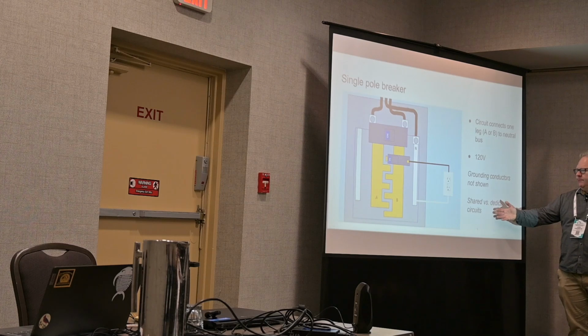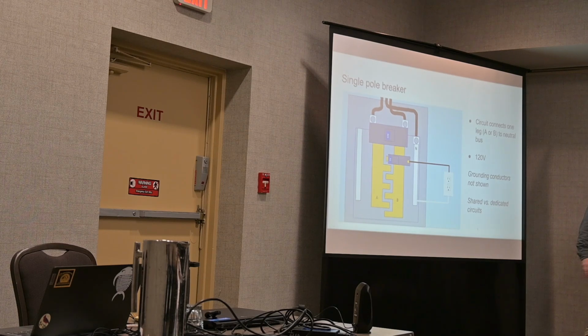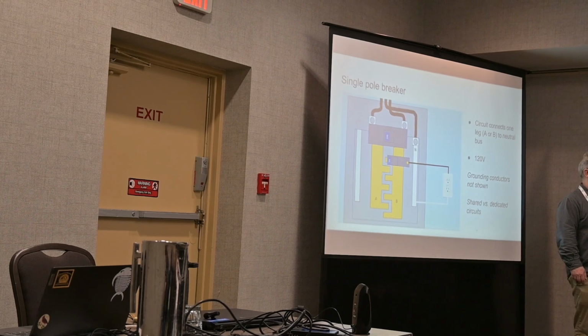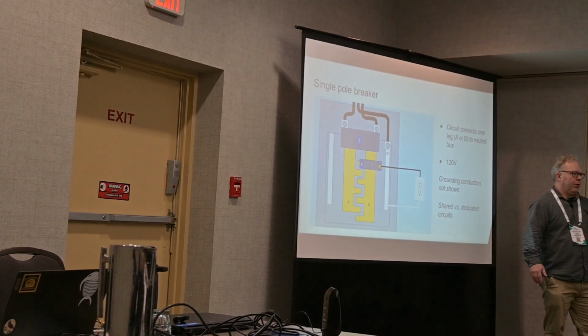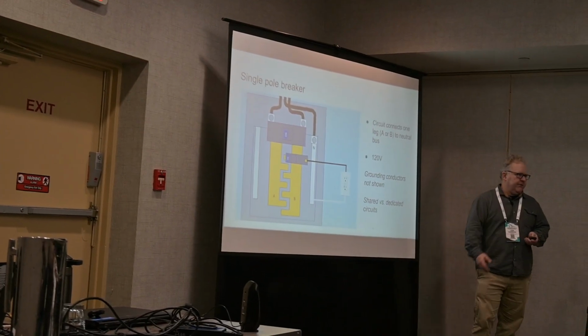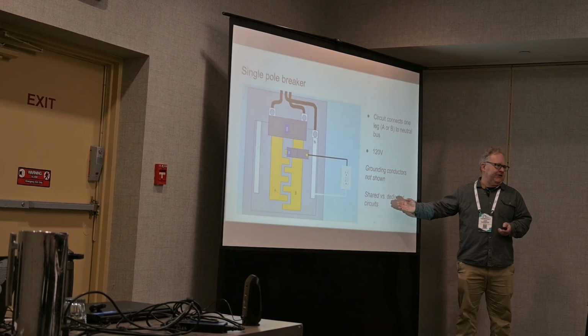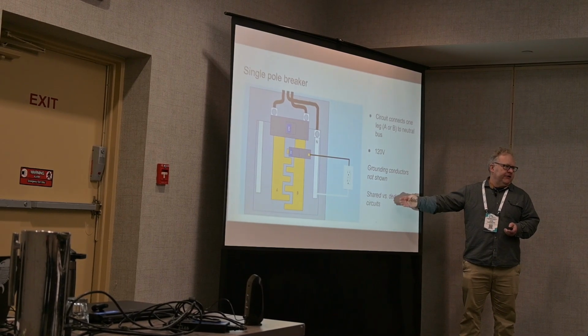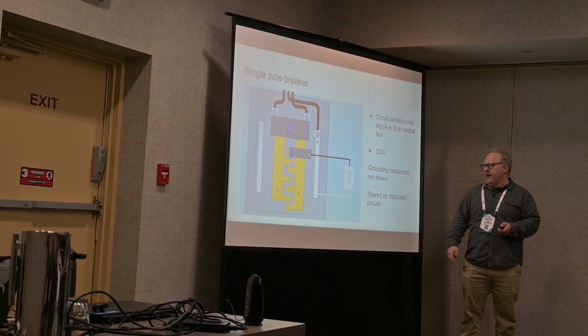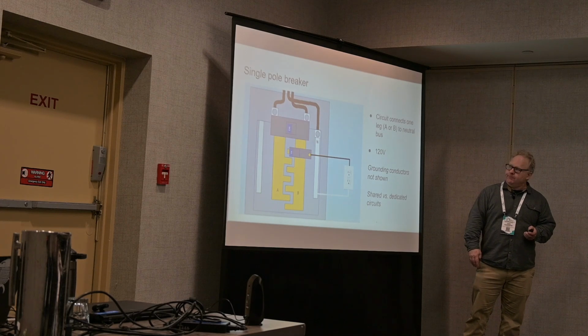With these circuits, we can have either shared circuits, ones in which we have multiple things plugged in. That's a typical residential plug circuit, a shared circuit. And we can also have dedicated circuits when we've got an appliance with a larger draw, like a sump pump or a whole house dehumidifier. The manufacturers are going to specify a dedicated circuit. That's one that is designed to only have one outlet for that device.